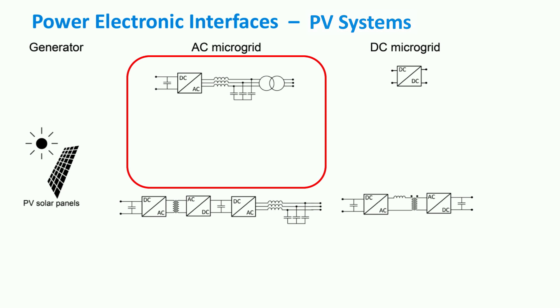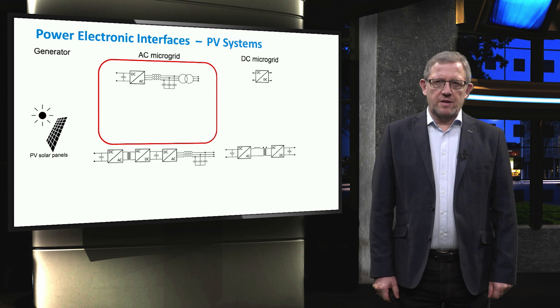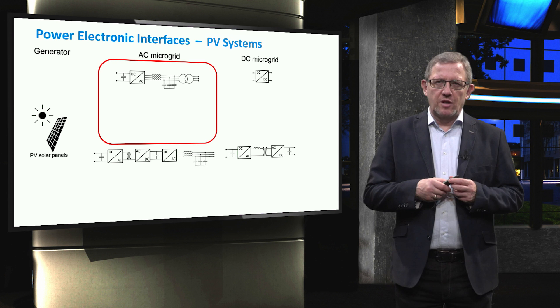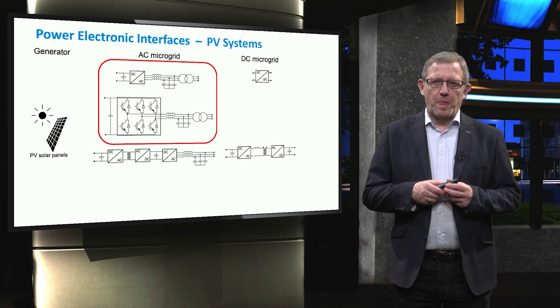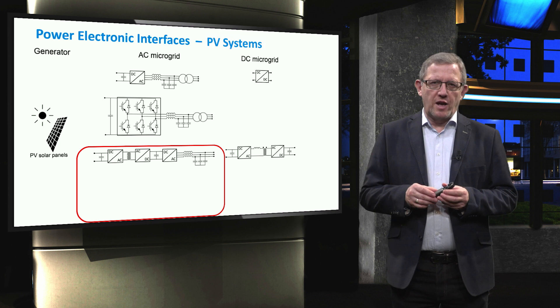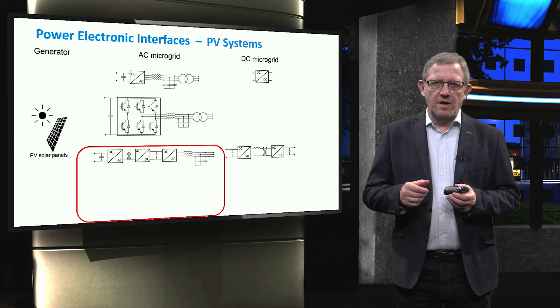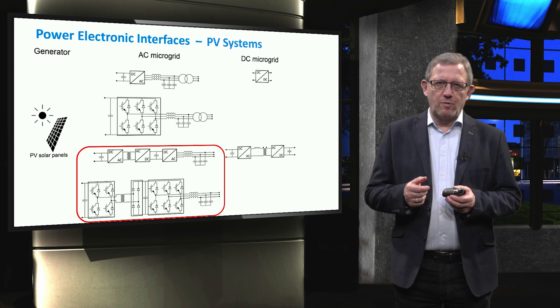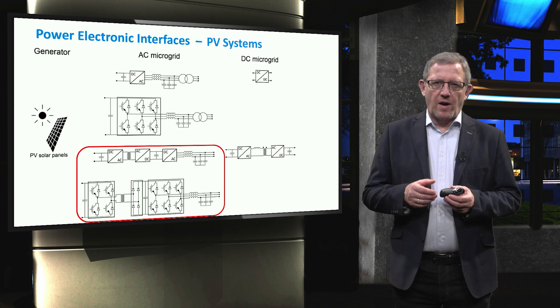This figure shows different possible power electronic interfaces for PV systems. To connect a photovoltaic unit to an AC microgrid, first it is required to invert the input DC voltage to three-phase AC using a common three-phase inverter. Then the three-phase voltage can be stepped up using a transformer, which is usually expensive and bulky. To eliminate the bulky transformer, it is possible to use a smaller high-frequency transformer, which also provides isolation. However, to do so, it is needed to increase the conversion steps: first from DC to AC, and then from AC to DC through a diode bridge. The high-frequency transformer is placed between these two converters. Finally, the DC voltage output of the diode bridge is inverted back to AC.